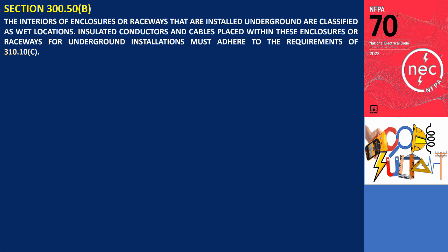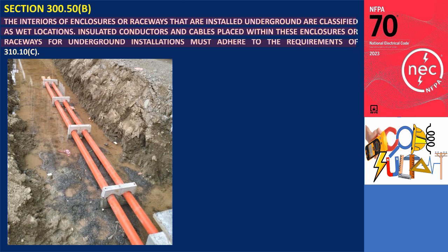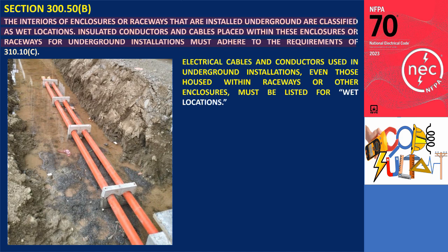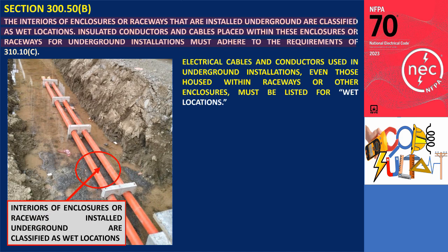Section 300.50(B) specifies that the interiors of enclosures or raceways installed underground are classified as wet locations. Consequently, all insulated conductors and cables placed within these enclosures or raceways for underground installations must comply with the requirements of section 310.10(C). This section mandates that all electrical cables and conductors used in underground installations, even those housed within raceways or other enclosures, must be listed for wet locations.